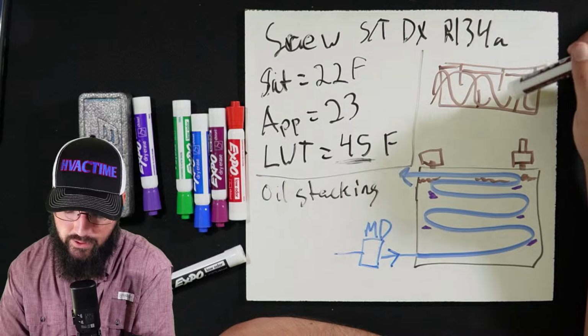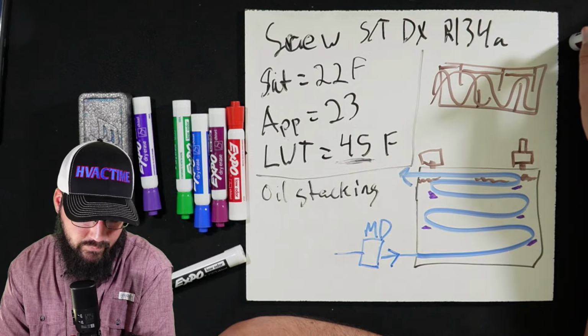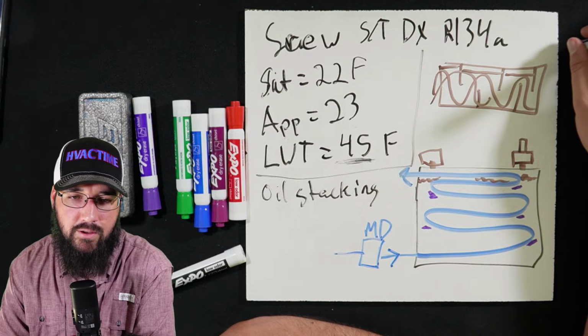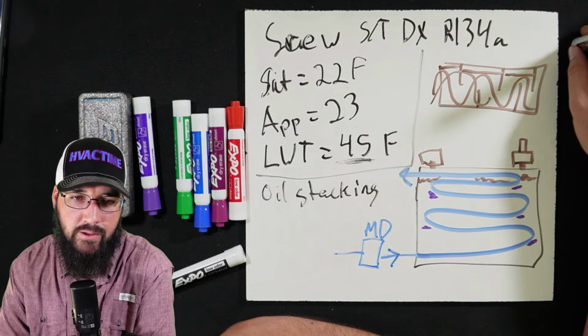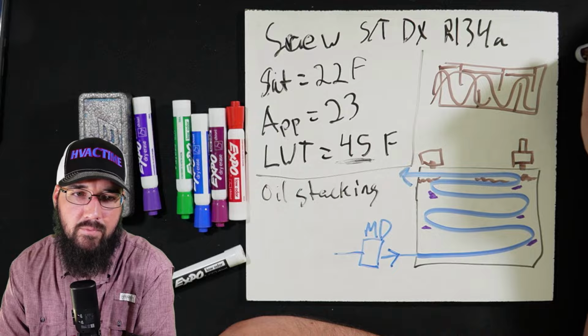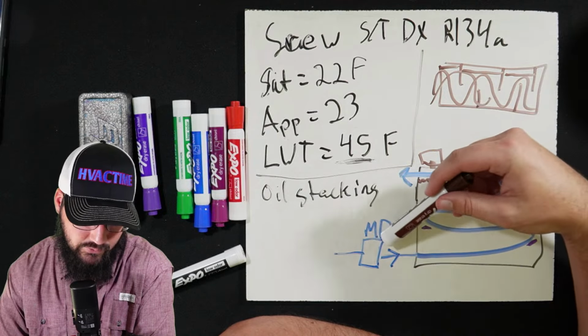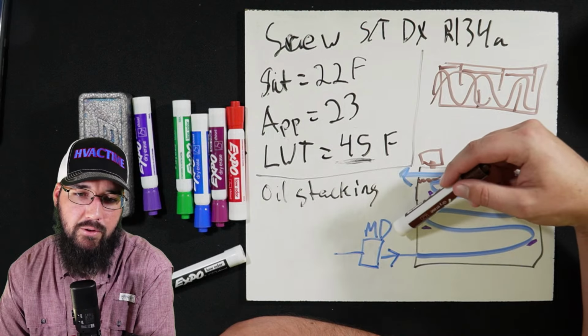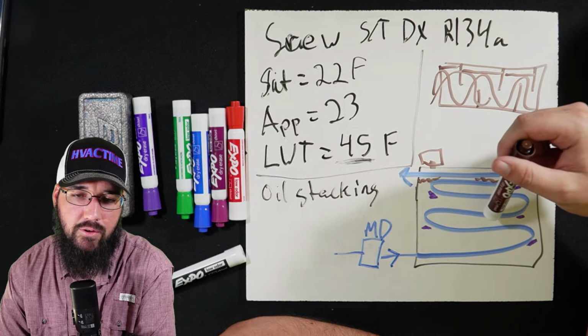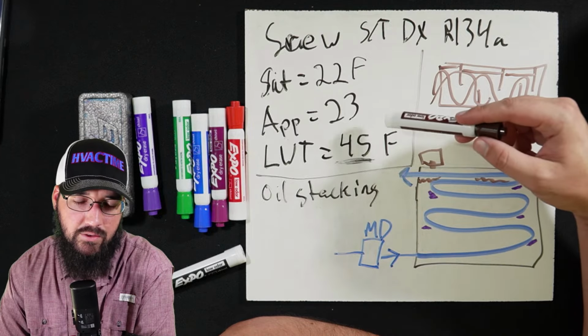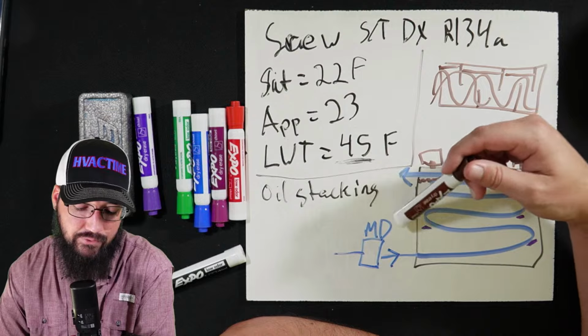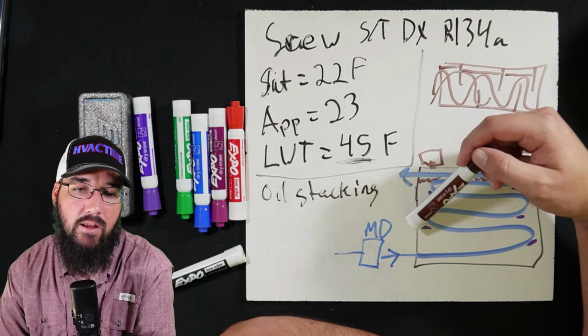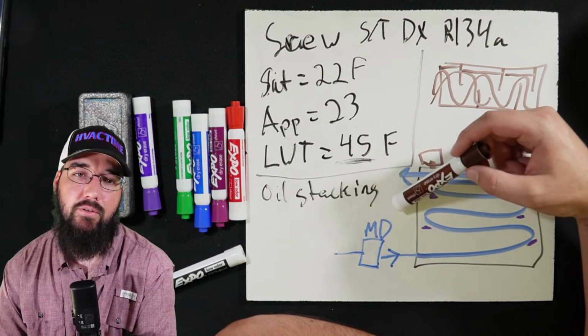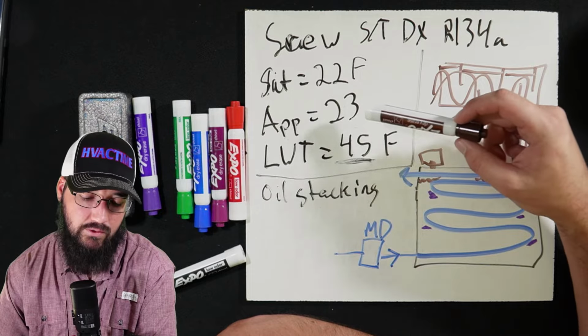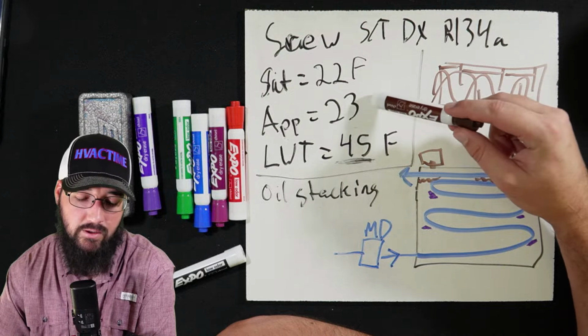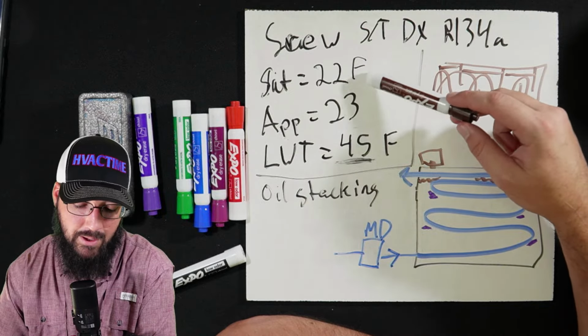Okay, what other options do we have? We have air trap, oil stacking. If we show good DP across the evap, we know it's clean. We know the charge is good. The only other option I could think of would be the metering device itself. If the metering device is starving the evaporator, you're not giving it enough refrigerant, that's going to cause similar issues. You can still have leaving water set point being made. It may not be a complete failure on the metering device, but it's failed just enough to cause the saturation issue. That is possible. Yeah, that's absolutely an option.